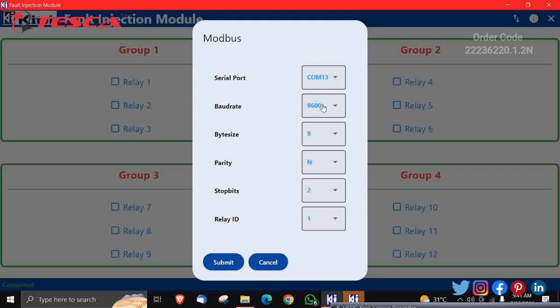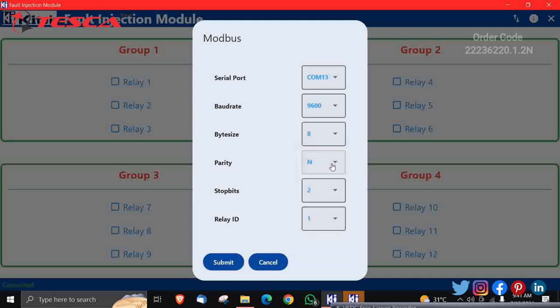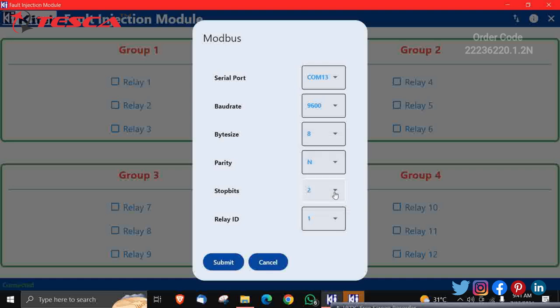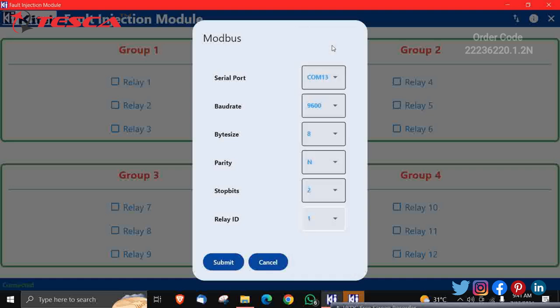Since the system's baud rate is 9600, byte size should be 8, parity should be N, stop bits I have taken 2, and relay ID it should be 1 because we are working on this. And submit it. So it has been saved.